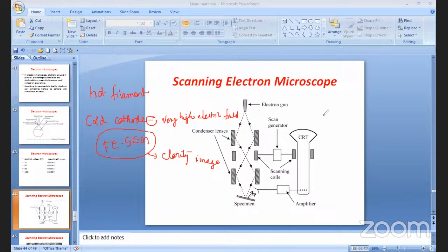The vacuum which we are keeping in the vacuum chamber will be in the order of 10 to the power of -2 to 10 to the power of -3 pascals or better, which is necessary for the normal operation of a scanning electron microscope.